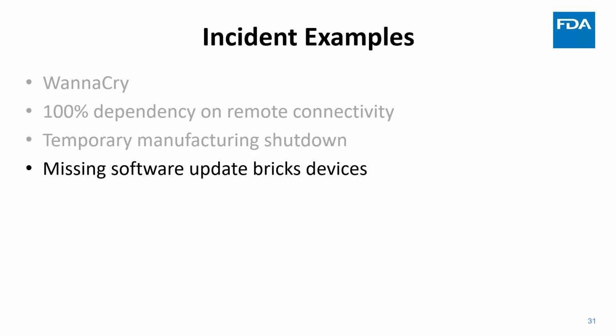This one was a fun one, mostly because this was an accident. We experienced a cyber incident with several medical devices where somebody just forgot to update a piece of software. And unfortunately, that piece of software was critical for authentication of users of those devices. So when that software essentially expired, the medical devices were bricked. They could not be used because you could not log into the device anymore. And it required a significant amount of effort and a visit by a field service engineer to actually fix the device. So this one was extremely disruptive.